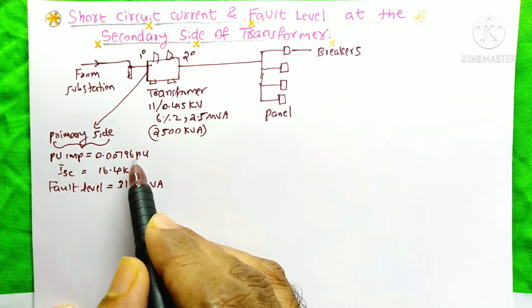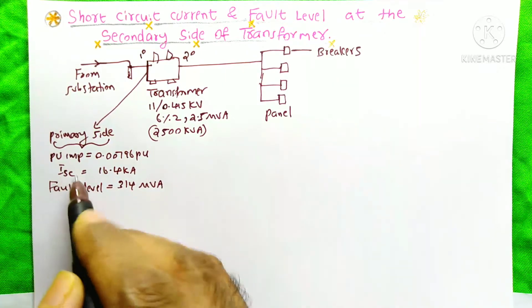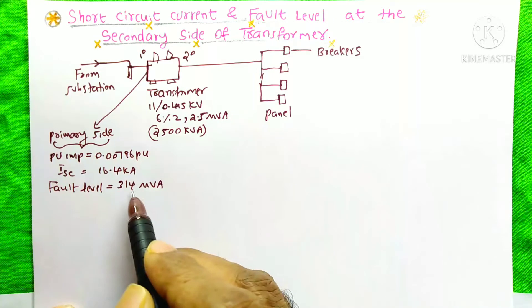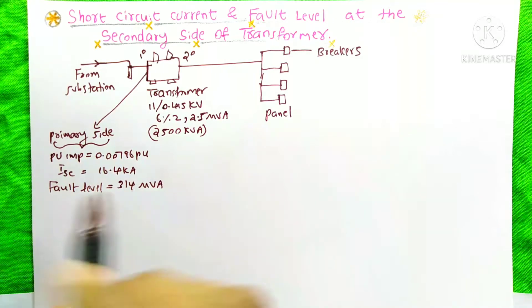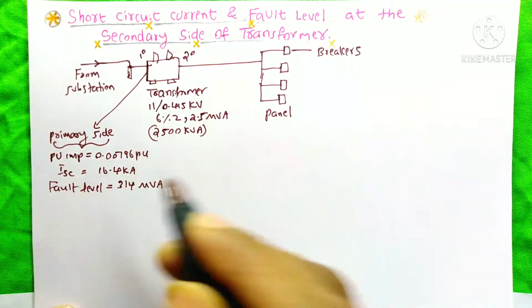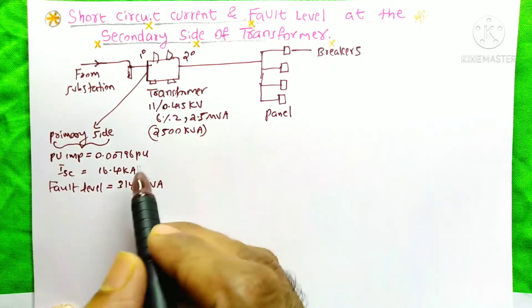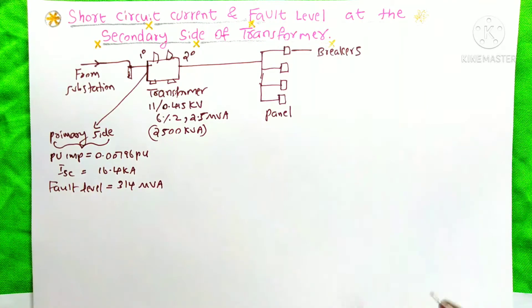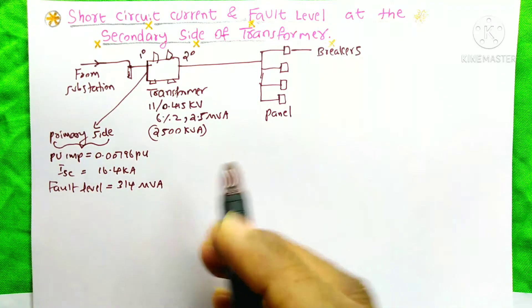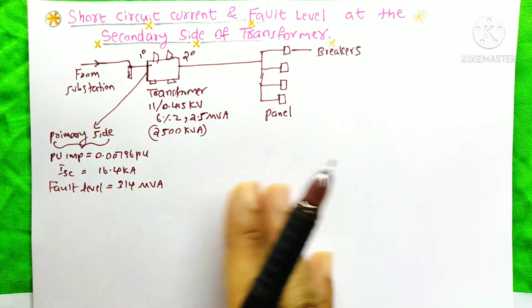This transformer's primary side data: the per unit impedance is equal to 0.00796 per unit, the short circuit current is 16.4 kA, and the fault level is equal to 314 MVA. This tutorial is actually the continuation of the previous video. If you did not see that video yet, I will give the link on the i-button and also in the description box. You need to see that video first, then only you will understand this video.